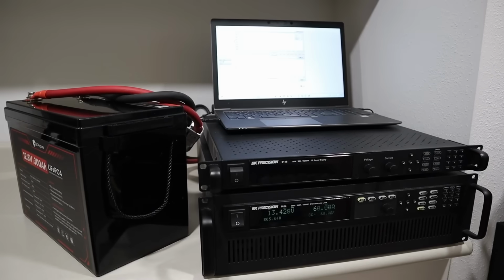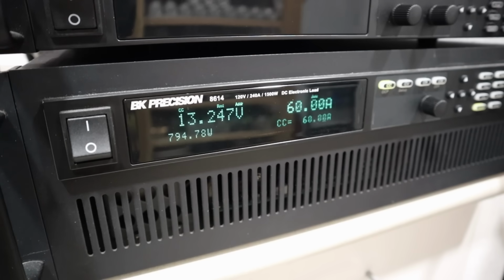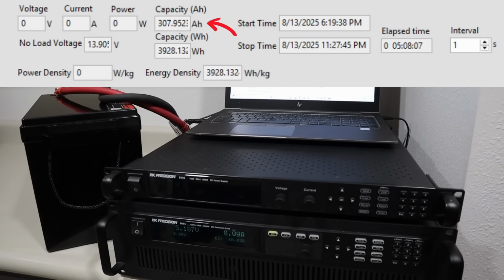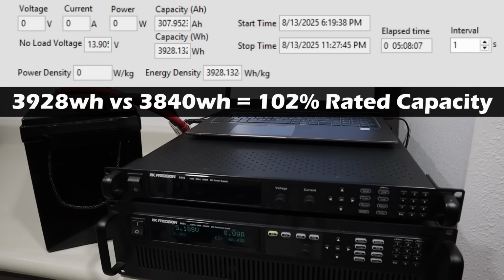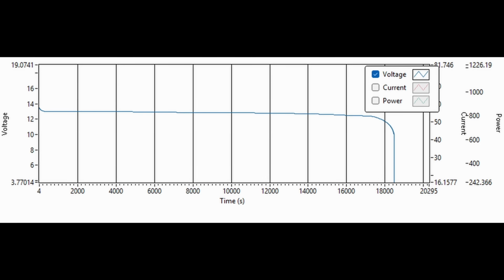Now first, I completed a capacity test on the battery with my DC electronic load. I had it set to a 0.2C rate or 60 amps. By the time the battery had shut off, I pulled a total of 307.9 amp hours or 3,928 watt hours. So we did pull over the full rated capacity of the battery. This result was around 102% of the rated capacity. Now I also tracked the voltage curve during this test just to make sure there wasn't any voltage sag, and you can see that the voltage curve is very flat throughout the entire test, which is good.